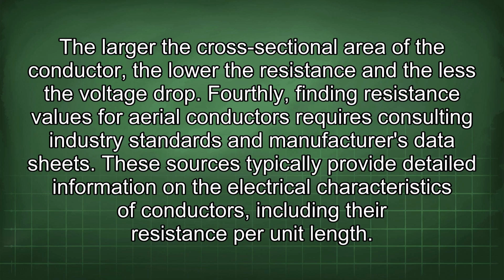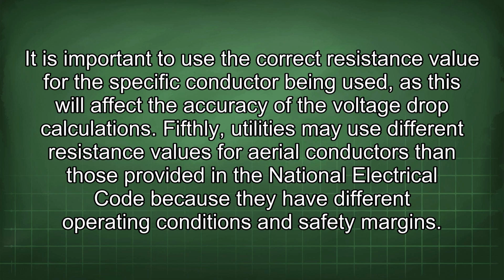Fourthly, finding resistance values for aerial conductors requires consulting industry standards and manufacturers' data sheets. These sources typically provide detailed information on the electrical characteristics of conductors, including their resistance per unit length. It is important to use the correct resistance value for the specific conductor being used, as this will affect the accuracy of the voltage drop calculations. Fifthly, utilities may use different resistance values for aerial conductors than those provided in the National Electrical Code because they have different operating conditions and safety margins.